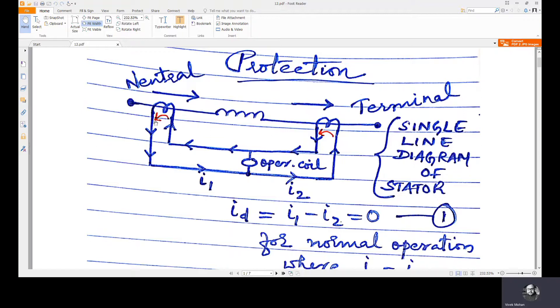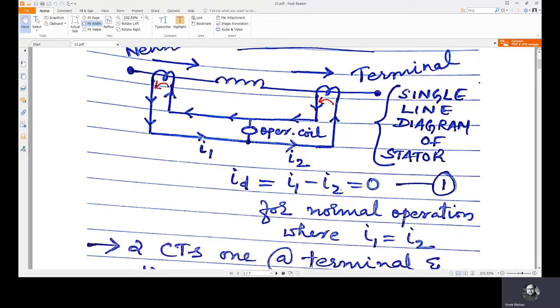We know that the secondary CT current will be in the opposite directions. Here, as the primary current is in this direction, the secondary current is in the opposite direction — here also it's in the opposite direction. You have a relay operating coil here. This is a differential relay which works on the differential current phenomenon, meaning if there is a difference in I1 and I2, that will flow through this operating coil. Both these currents are in the same direction and I1 and I2 are the same because these primary currents are the same. So ID, the current through the differential operating coil, equals I1 minus I2, which equals 0 for normal operation.